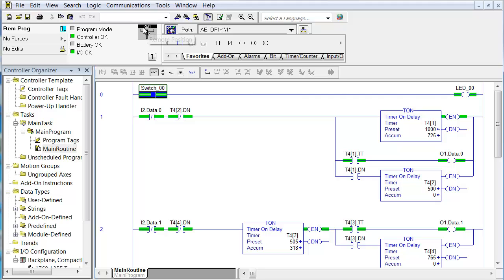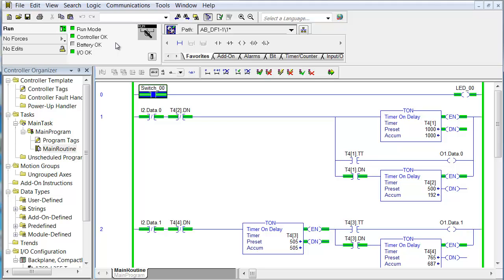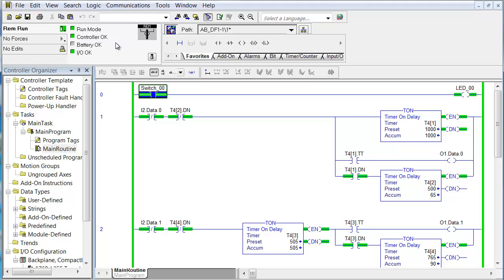Now pay attention to this key switch symbol right here — the color and the text. As I use the key switch, notice that it rotated over to program. You're in the program mode. Back to the center position, the key switch says remote but you're in remote program. The other direction is the run mode, but we want to switch back to the remote position. The key switch should always be left in the center position so you have remote access to the processor.